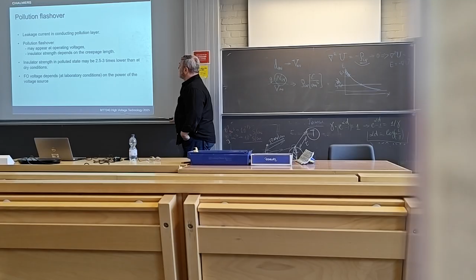It's aging for polymers, that's for sure. Ice and snow. That's how this could look like. Very typical for Canada, especially in the northern territories, where the complete line is just covered with tons of ice. They have huge safety margins for insulator strings in this case. Wind: transport and deposition of moisture. Lightning causes flashover. These are weather conditions which may affect the insulation performance. Pollution flashover. Just very quickly, I will not tell much about this because time is limited. So it's all about leakage current and creating conductive layers. It may appear under operating voltages or overvoltages. That may also be a factor.